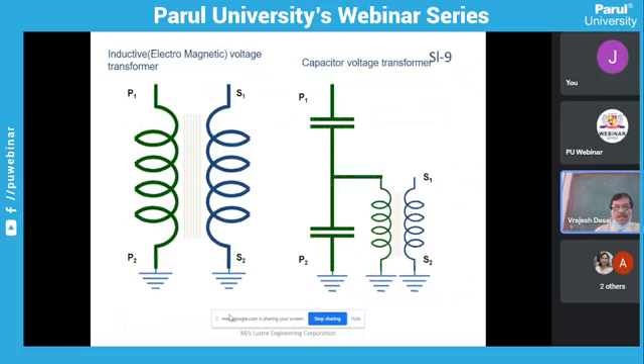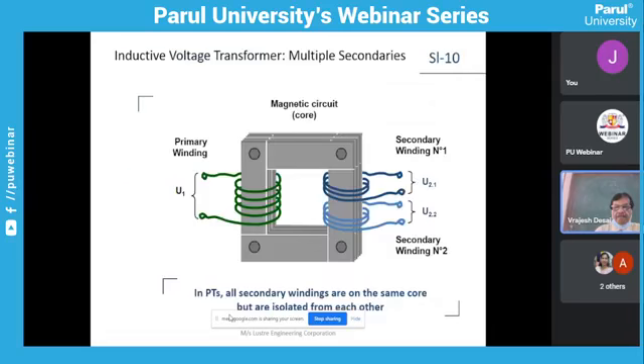Applied to the divider. We will see the detailed slide, the concept of a capacitor voltage transformer. This is a general view of the inductive electromagnetic transformer. It has primary side coils and secondary side coils. In a capacitor voltage transformer, you can see the two capacitors. In between the two capacitors, a small intermediate PT is connected. This is an inductive voltage transformer. Here, the core is the same for all the windings.